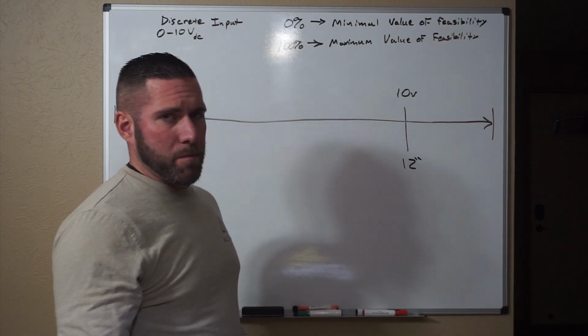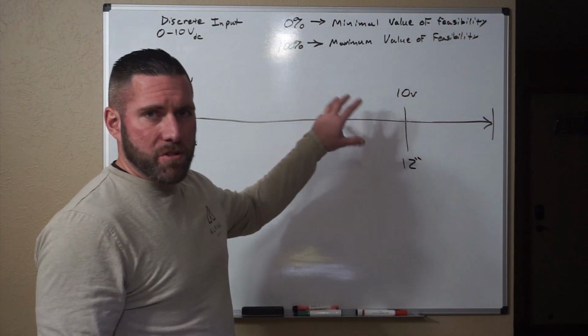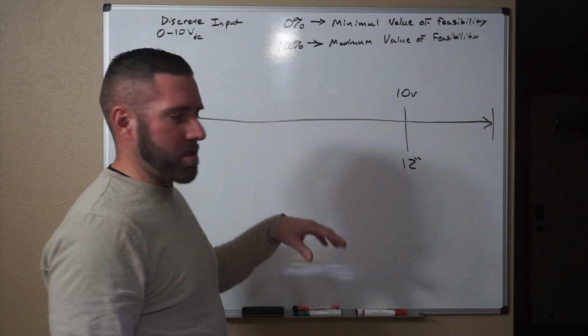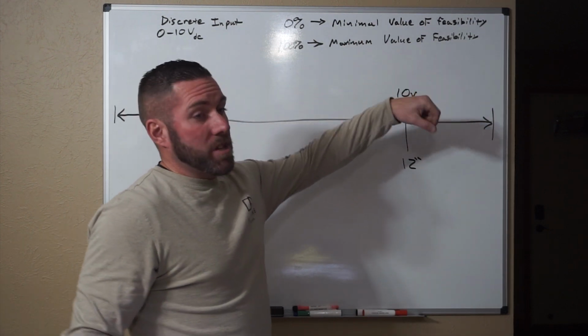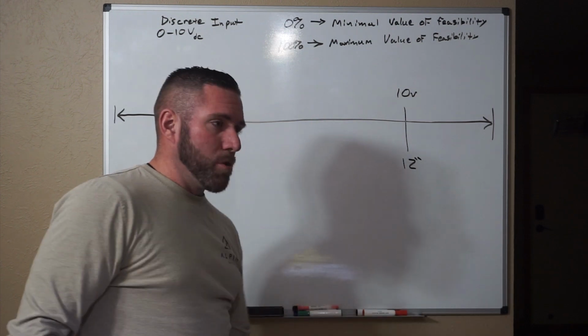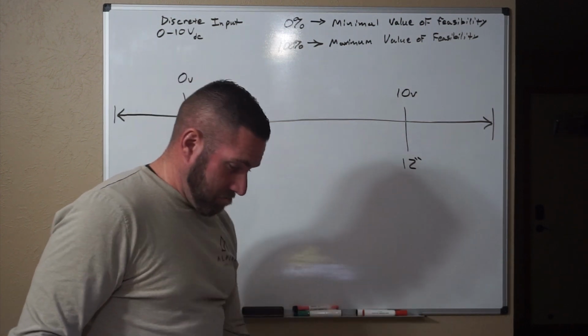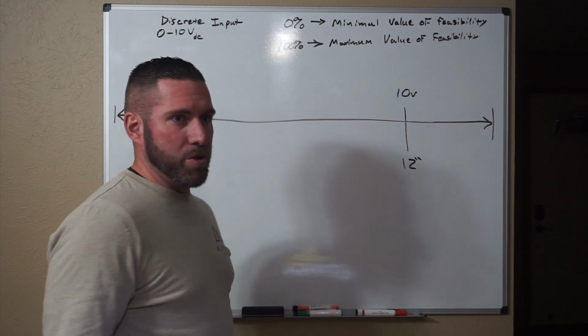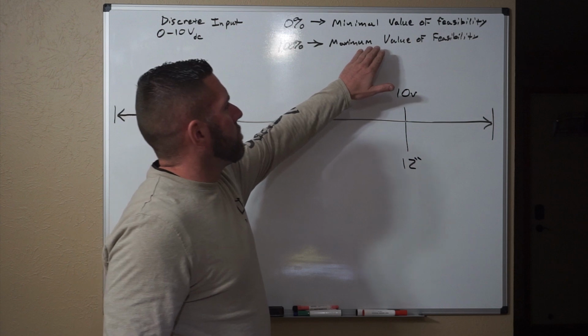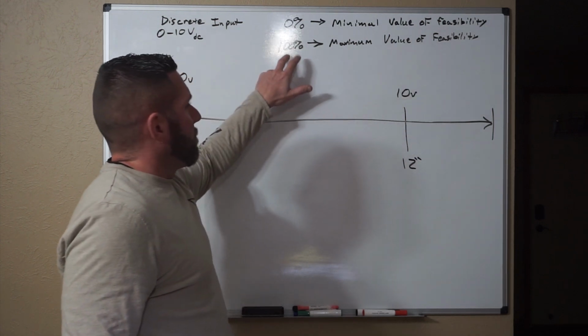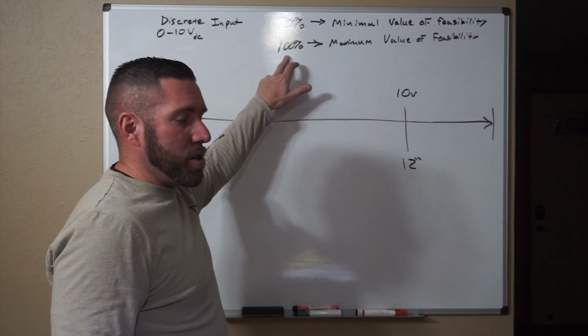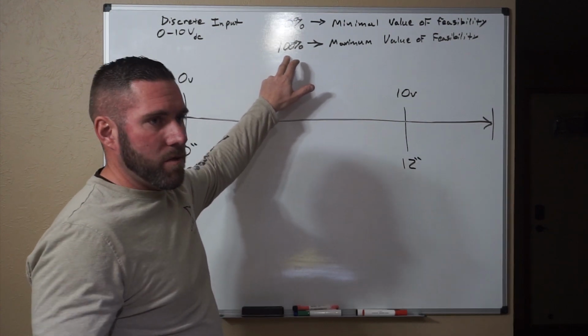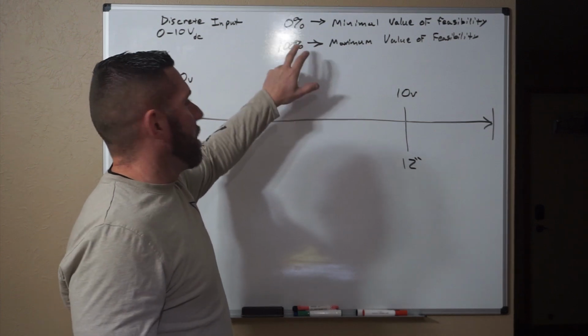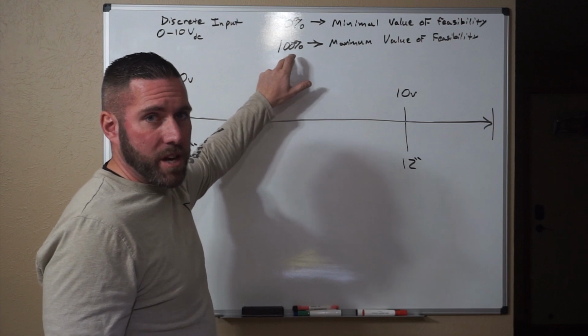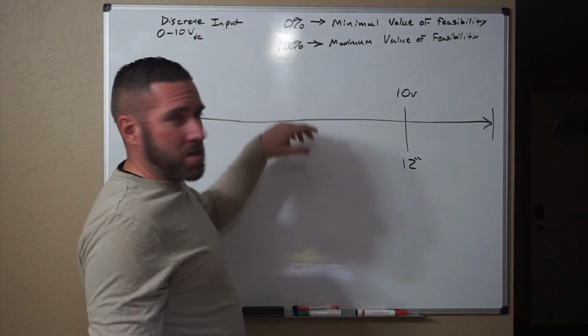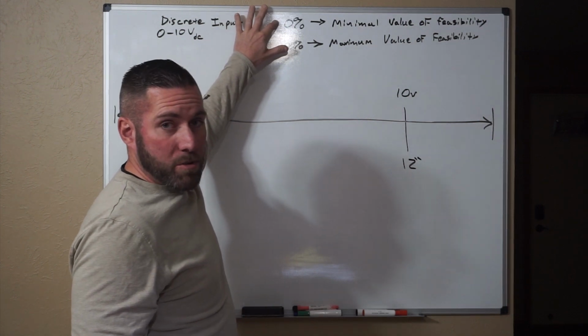100% in some cases if you weren't feeding a pump exactly. This is kind of a universal term and it is written how it needs to be written depending on the system you're designing. When we say maximum value of feasibility, that could also be if there's a valve at a really low place that's taking on a lot of pressure from just the water column effect, which is rho g h, and we would figure out that the maximum value of feasibility, if you put a high alarm on this, what you're saying is that you may get leak by on a globe valve or a gate valve, possibly a butterfly could open by accident if you have too much head on the suction side of a valve. So this would be where the plant wants it to stop. This is where the plant wants the lowest range to possibly be.